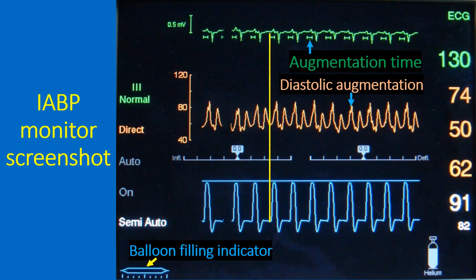On the IABP screen, the uppermost green tracing is the electrocardiogram, which is used to time the inflation and deflation of the balloon. The augmentation time is marked just below the tracing to indicate the exact point of inflation and deflation. The arterial pressure tracing just below that indicates the diastolic augmentation.